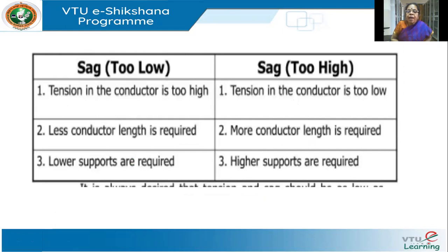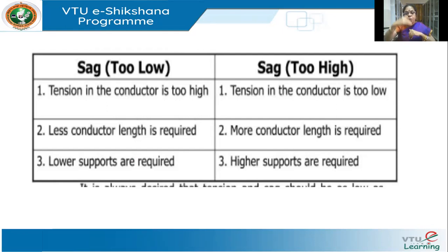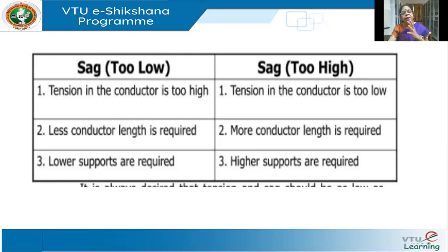If the sag is too low — very small, tightly stretched — tension will be very high, conductor length required is less, and you can have lower supports. However, if sag is too high, tension will be too small, you will require a lot of conductor length, and support height will have to increase because the conductor must not touch a building, tree, or a loaded lorry passing beneath. So the sag must be neither too high nor too low.